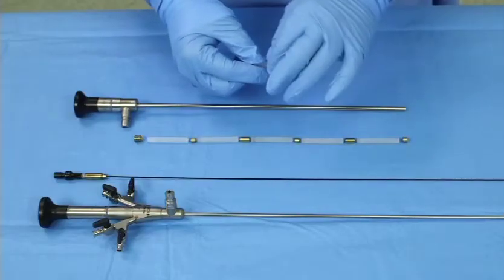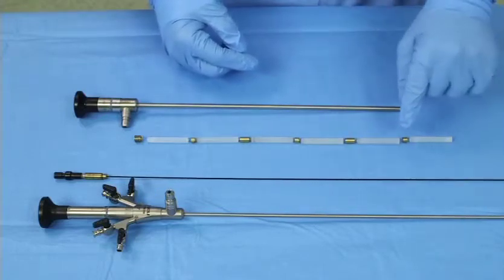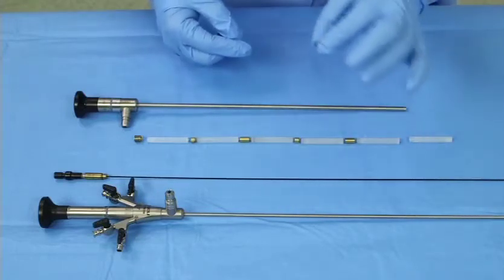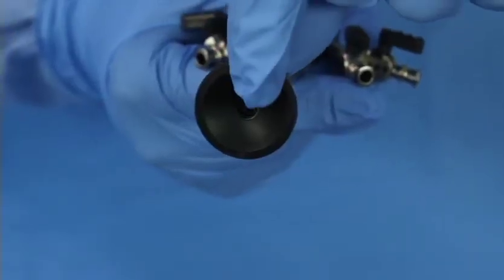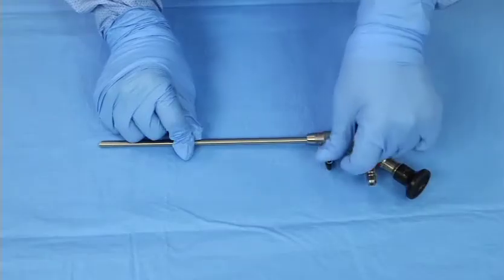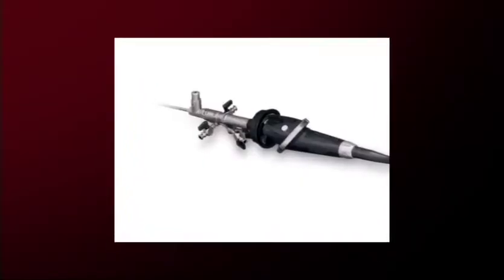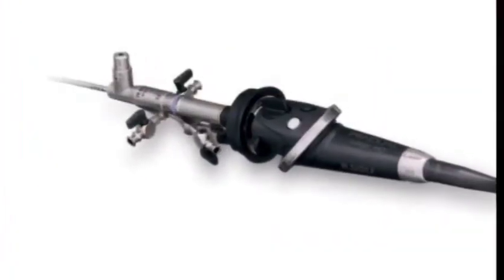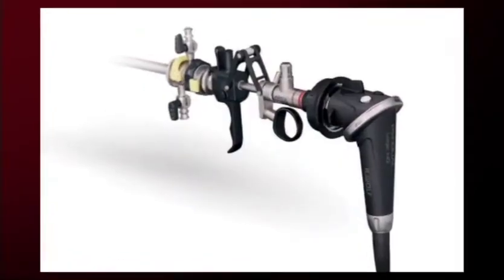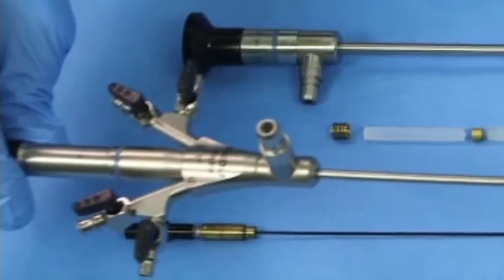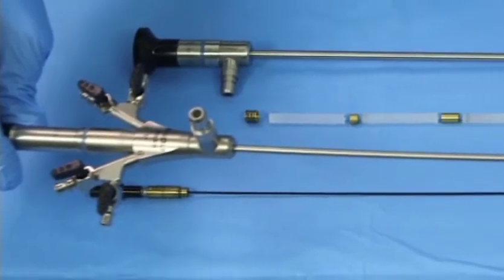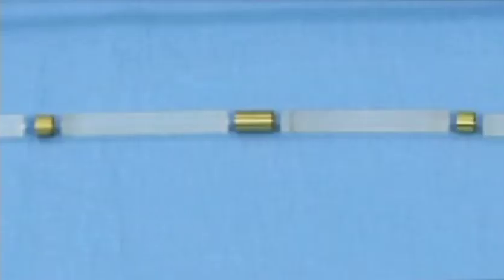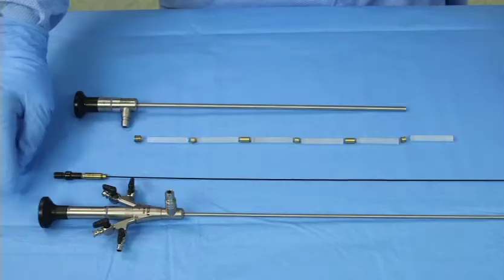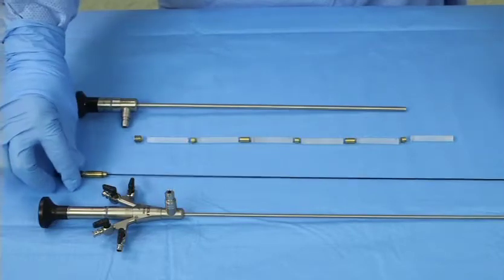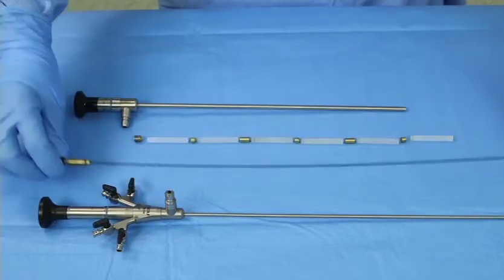Some diagnostic endoscopes utilize stiff glass rods to transmit the image from the surgical area to the endoscope's eyepiece. An operative endoscope has both visual and operative capabilities because the sheath is integrated into the scope. This integrated sheath allows instruments and fluids to enter a body cavity during a surgical procedure. The endoscope shown here is a type of operative scope that uses fiber optic bundles to transmit the image from the operative area to the eyepiece instead of stiff glass rods. The fiber optic bundle allows the scope some flexibility to move through the anatomy more easily.